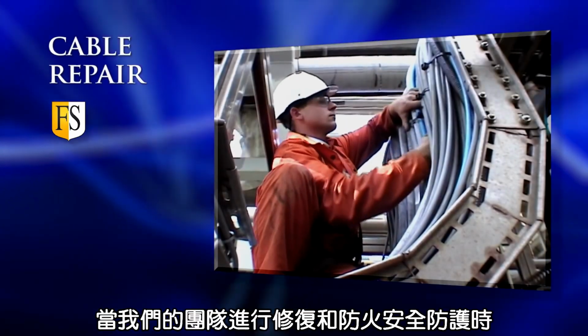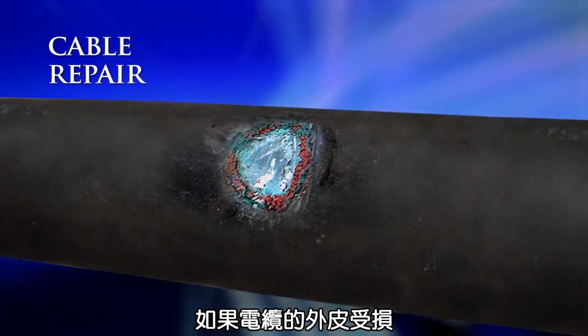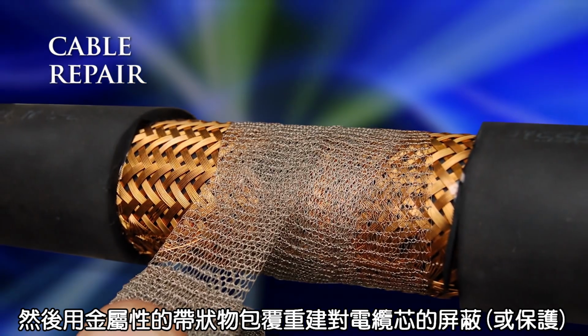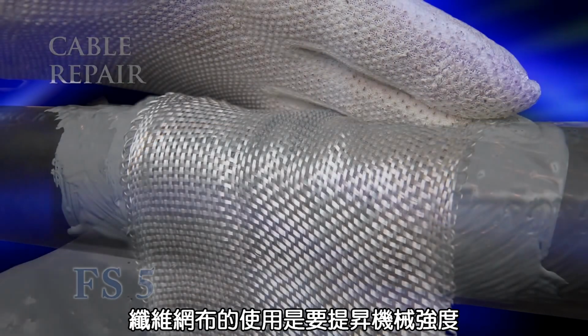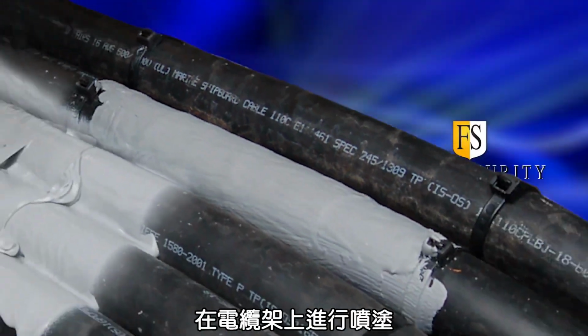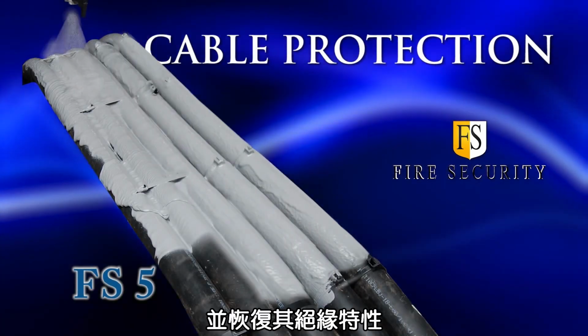When our team performs a repair and fire protection, we clean the cables using special cleaning materials or water. If the outer sheath and the cable's screen is damaged, we clean the affected area and rebuild the screen by use of a metal shielding tape. We then apply FS5 coating. A fibre mesh is used to gain mechanical strength and as support for the coating. The repaired cable is tied in place and coated with the other cables on the tray. The excellent properties of the FS5 coating ensure that the insulation property is completely rebuilt.